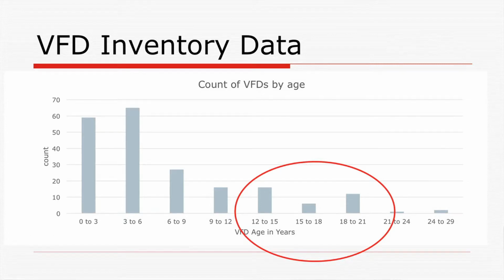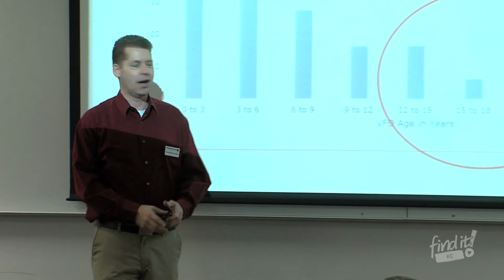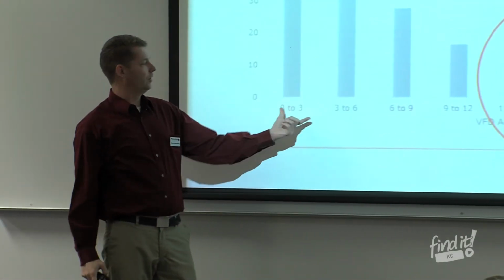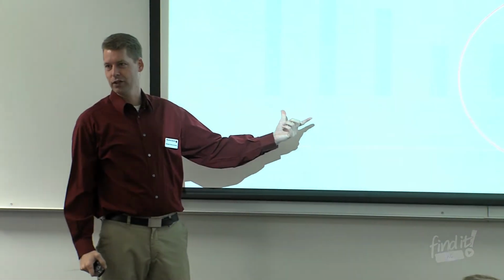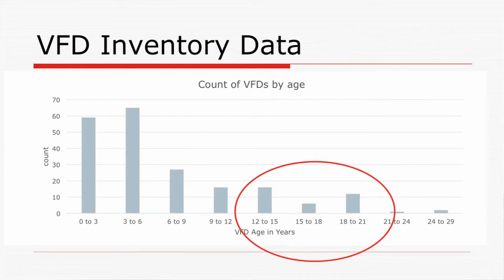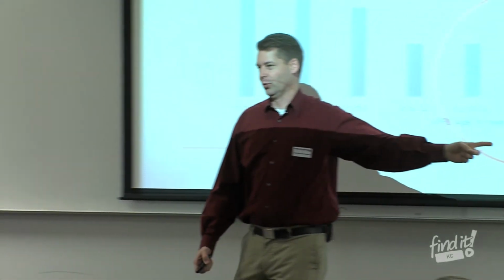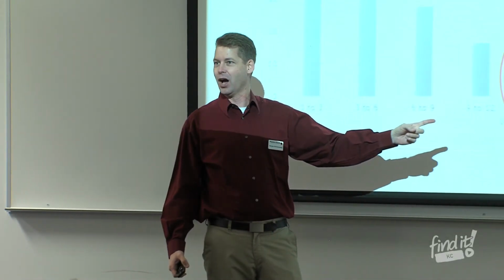So this is a resultant chart of that university's VFDs. And you'll notice that it's age in years on the bottom and the number of VFDs they have for that age. Most of their VFDs are in the 0 to 6 year range. That's because they've done lots and lots of projects recently, and everything comes with a VFD. Now, if you go out to 25 years old, nobody's putting VFDs on anything 25 years ago, so there weren't many out there. They do have some that are 24 to 29 years old, and those are the workhorses that have just been out there forever and the anomalies.